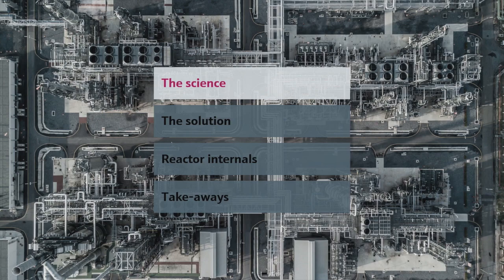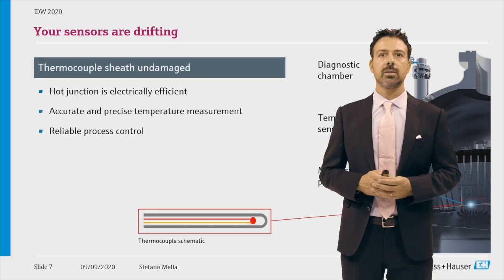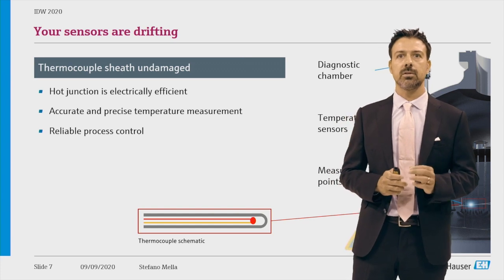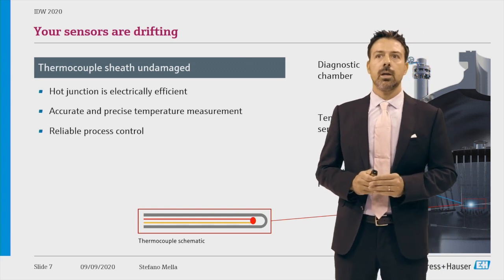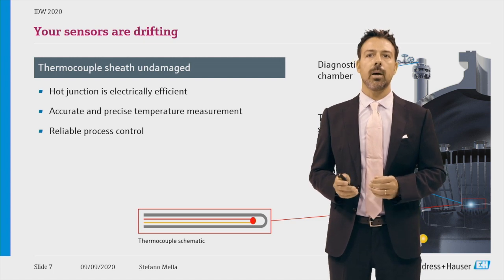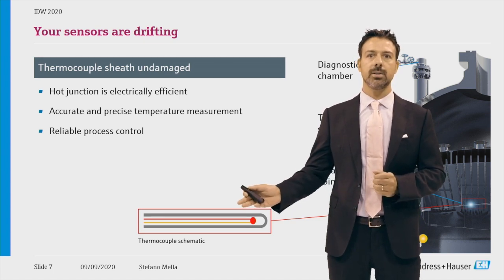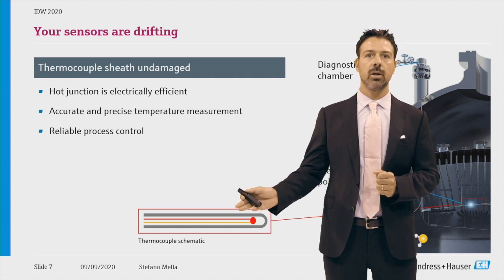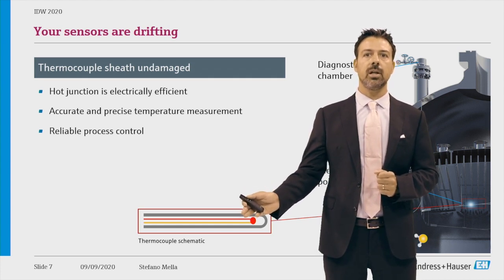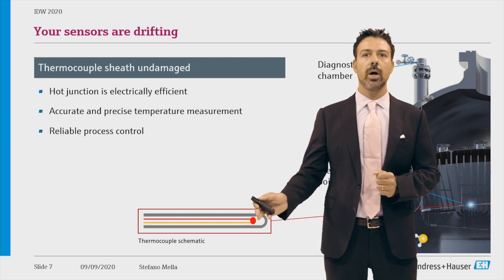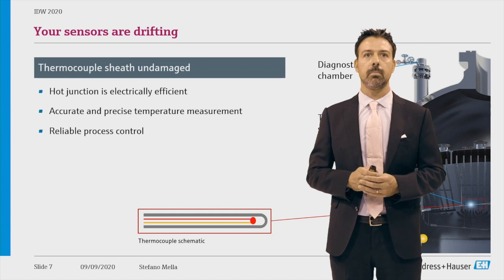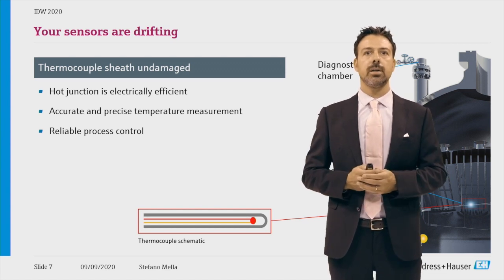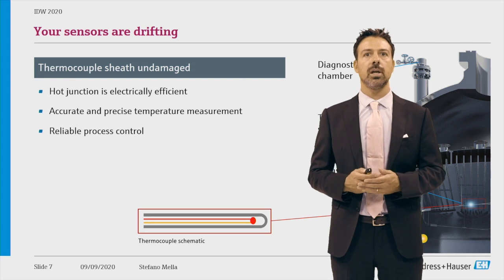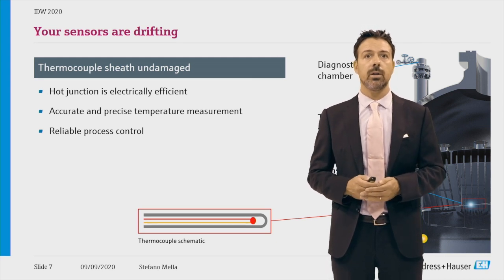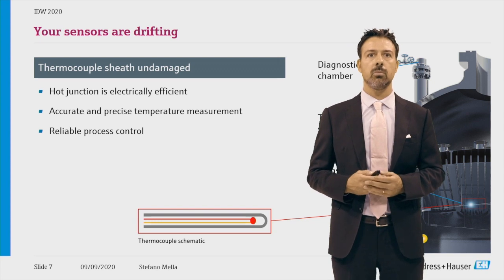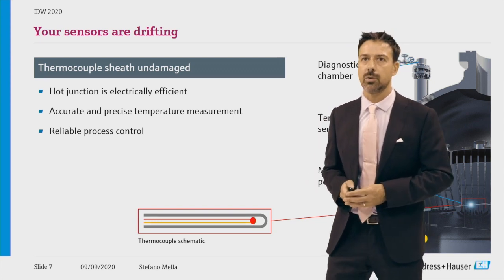So let's start with the science behind thermometers and more specifically temperature sensors in the form of thermocouples. So here we have a typical thermocouple. You might see it's quite a simple device. It's composed of an outer metal sheath, and inside we have an electrical circuit with a hot junction, and the white part is mineral insulated powder. So when the thermocouple is undamaged, then the hot junction is electrically efficient, it's accurate, and it can enable precise temperature measurement for reliable process control.